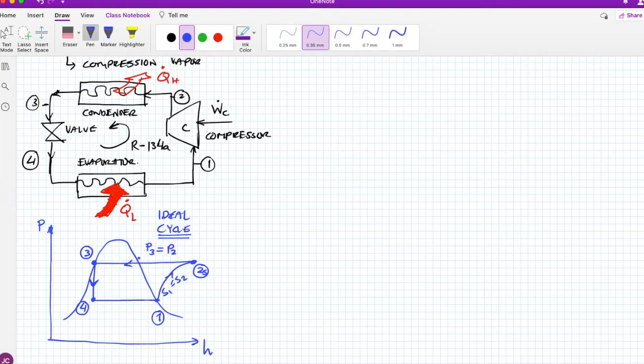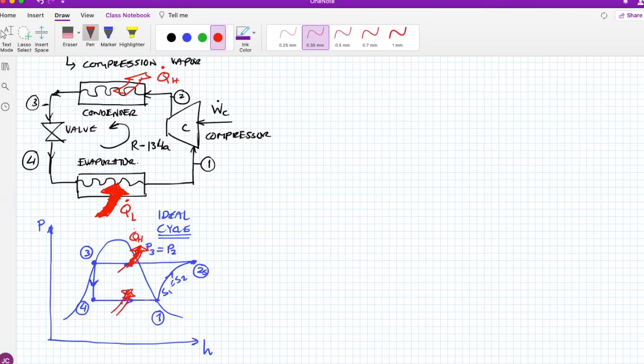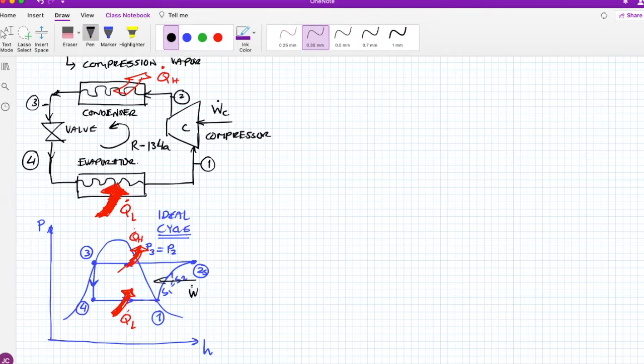From point 3 to 4, the valve depressurizes the refrigerant — it reduces the pressure while keeping enthalpy constant. The process is isenthalpic, hence the vertical line from 3 to 4 on the pressure-enthalpy diagram. Then from 4 to 1 in the evaporator, QL enters the cycle from the food, and work enters at the compressor.